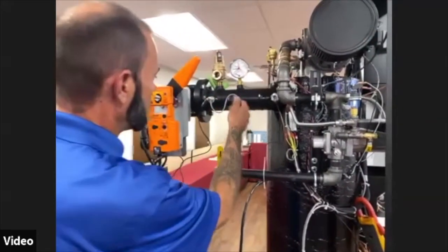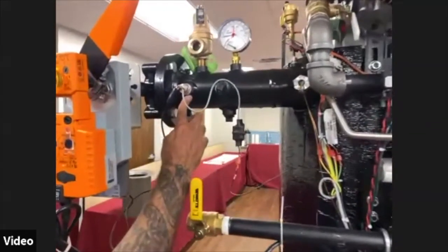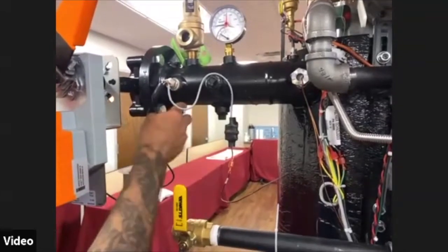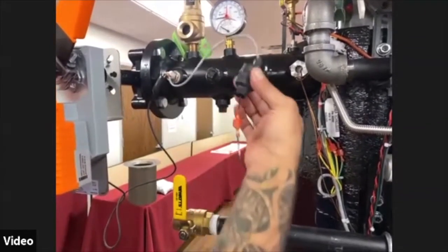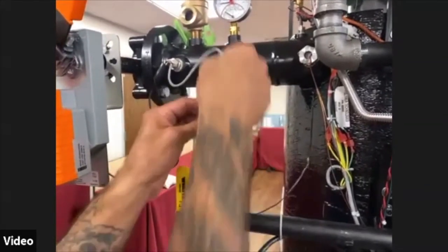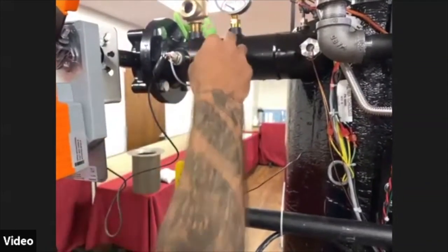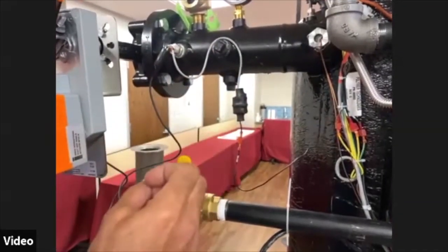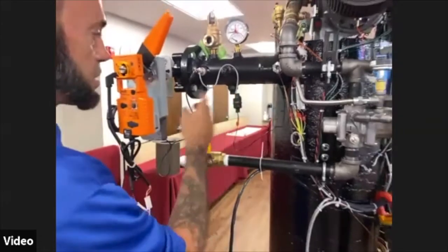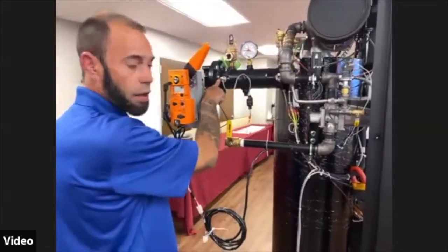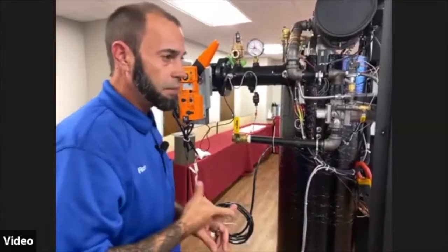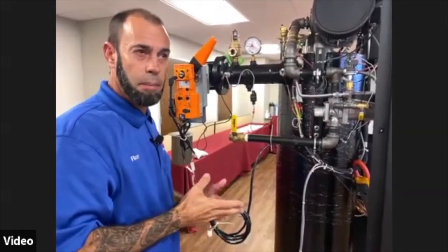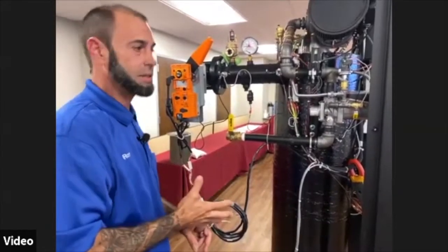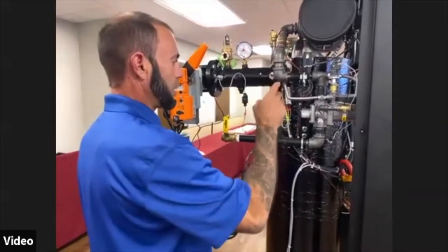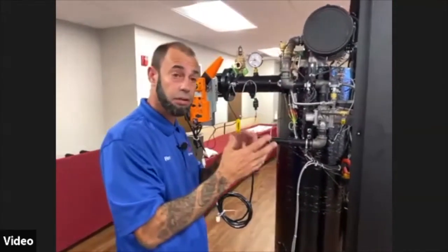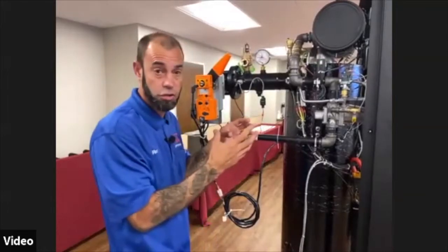Coming across the header, down just below it, this will be our low water cutoff. Our low water cutoff sits right inside of our supply header. It also has a capacitor connected to it to bleed the voltage off of it. This can be tested again with the front panel like we talked about. We also can do a resistance test on this from the low water cutoff probe to the P5 19-pin connector, pin number 6, I believe it is. Resistance from there. So that's on the back of the Edge Control. That P5 pin connector is on the back of the Edge Control. Okay.